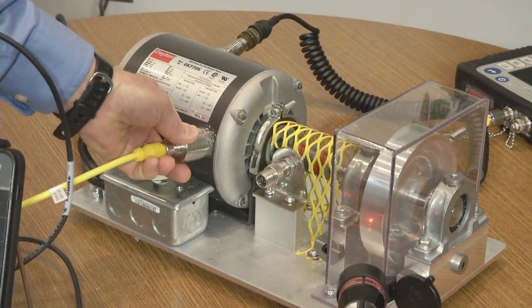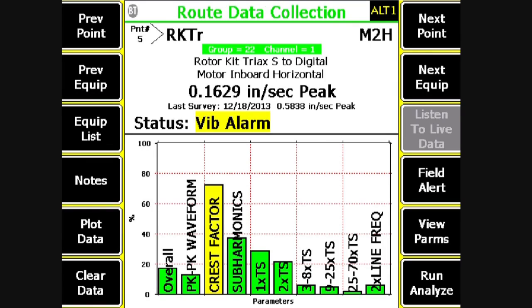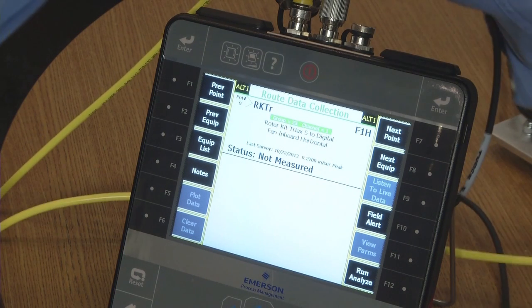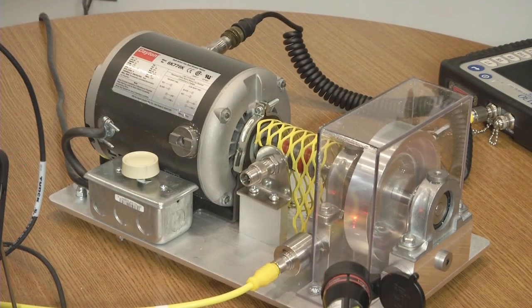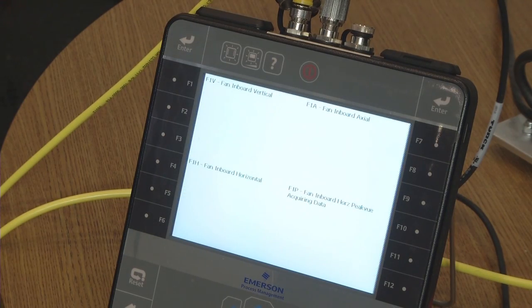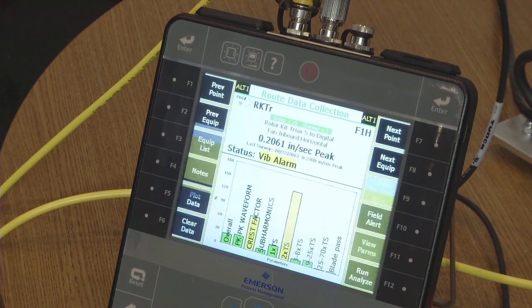I move the Triax to the motor inboard position and press enter. Data collection starts, and all three axes plus PeakVue are complete. It then asks me to advance to the fan inboard position. I press enter to start data collection, and data collection is complete.